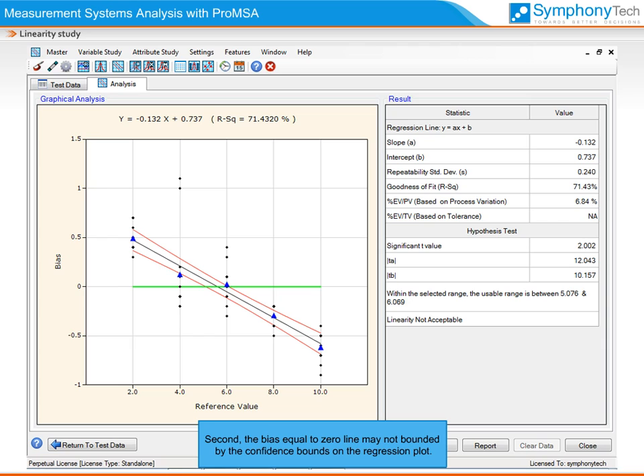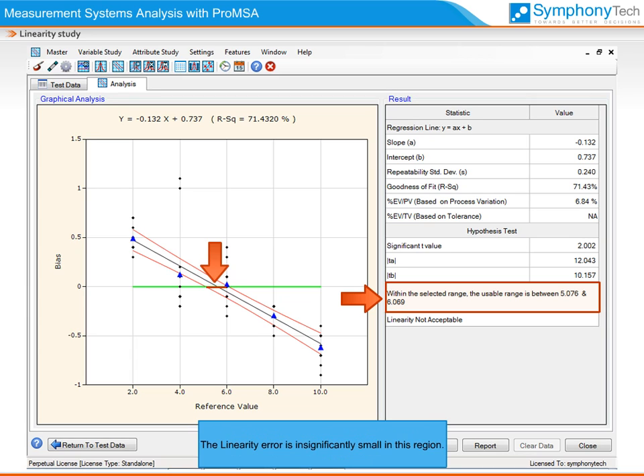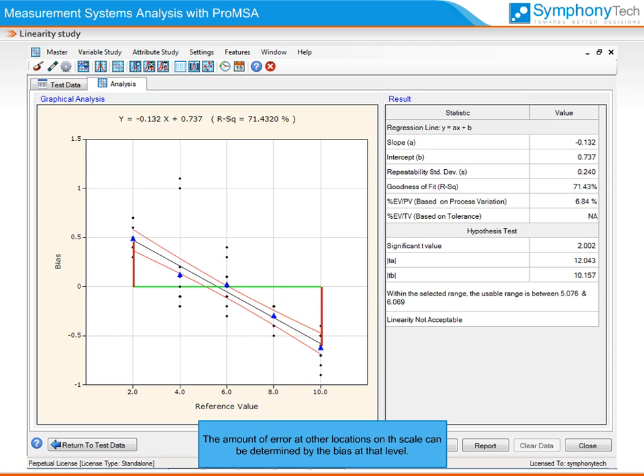Second, the bias-equal-to-zero line may not be bounded completely by the confidence bound on the regression plot. In such a case, Pro-MSA analysis gives the range on the scale where the bias equals zero is contained within the confidence bound. The linearity error is insignificantly small in this region. The amount of error at other locations on the scale can be determined by the bias at that level, and bias correction factors can be applied to each reading taken at those nominal points on the range.